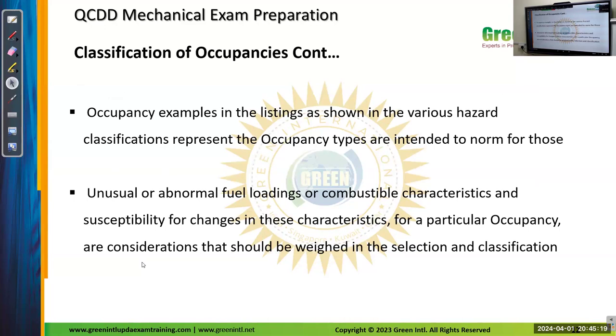So the occupancy examples listed, as shown in the various hazard classifications, represent the occupancy types intended to be normal. Unusual or abnormal fuel loadings or combustible characteristics, and susceptibility for changes in these characteristics for a particular occupancy, are considerations that should be weighed in the selection of classification. So the main aim of this classification is to know the hazard level. Only based on that hazard level can we design the entire system.